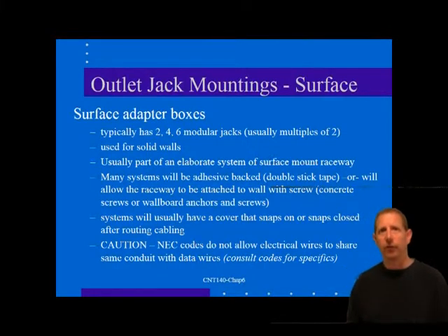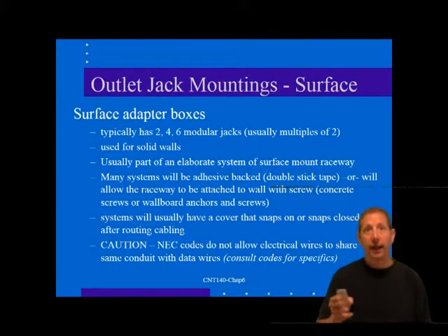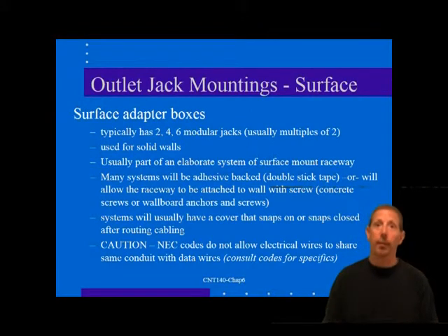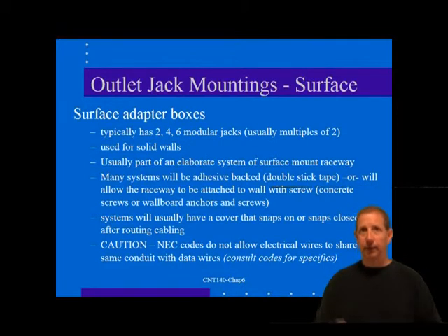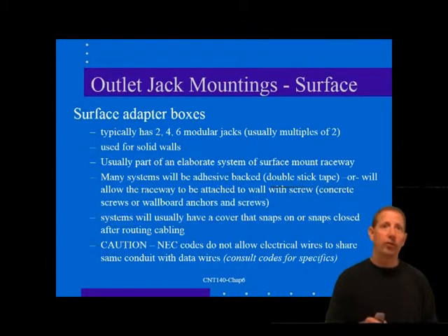You can see the code books for a detailed explanation of when and where this can be done. Now bear in mind that the run-of-the-mill square power pole that drops from the suspended ceiling to a work area rarely meets this test. Even though there's plenty of extra room inside the telecommunications cable, some modular furniture may have the same problem, as the wiring channel may be occupied by Class 1 wiring. In such cases, you may have to run telecommunications wiring external to the wiring channel.